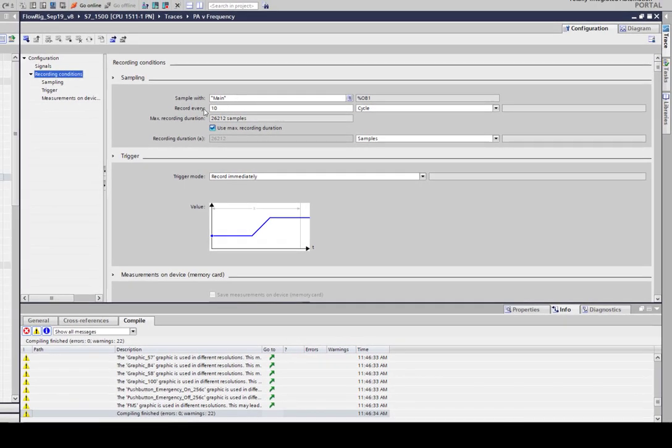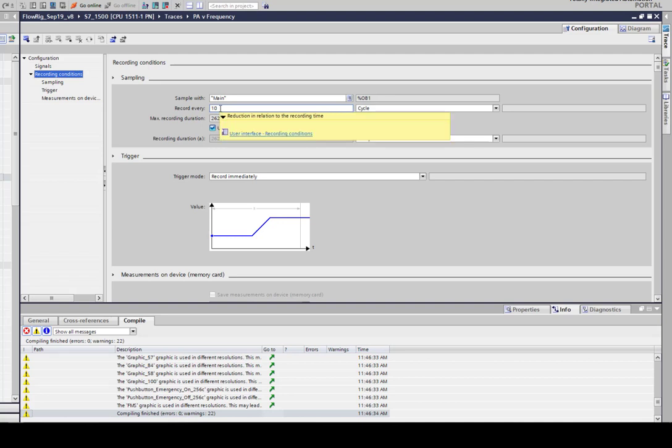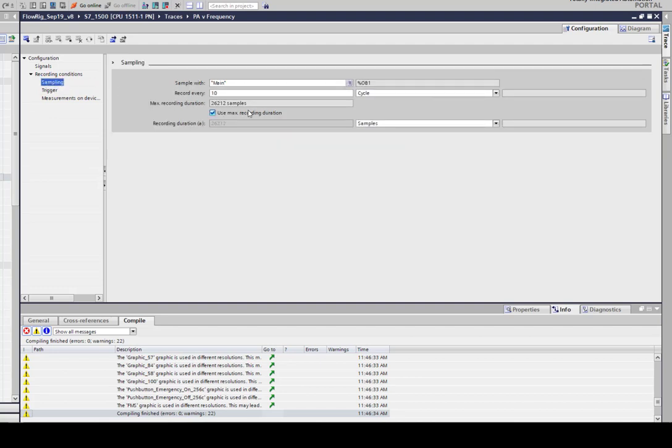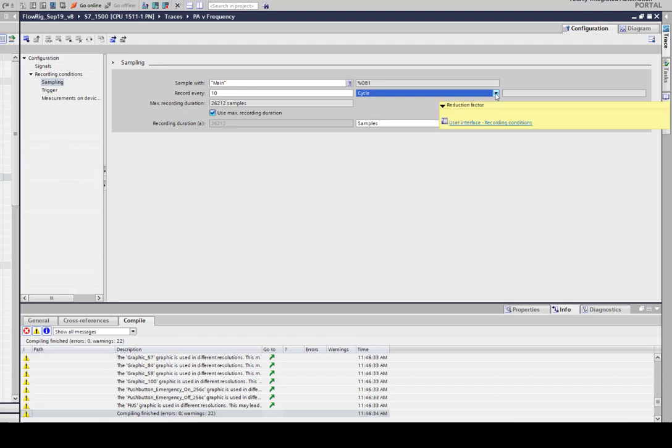You can change how much it will store in the logger. You can also have a trigger which is quite nice so if you think you've got a fault you could start recording. Or in this case I could start recording as soon as the flow meter registers the flow, but it will fill up the way I've got it sampling. But you can have it so it cycles and re-records over itself. So in this instance I'm taking a sample every 10 cycles of my code and there's not much code so it's going to be relatively fast as you'll see in a minute.